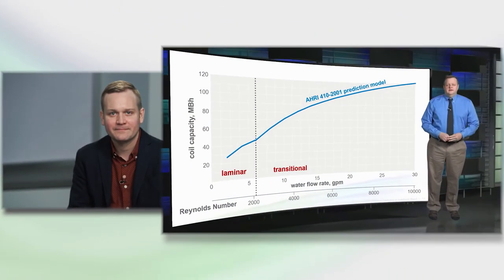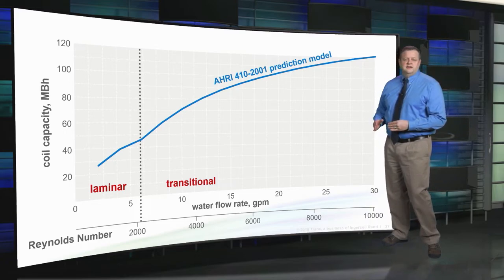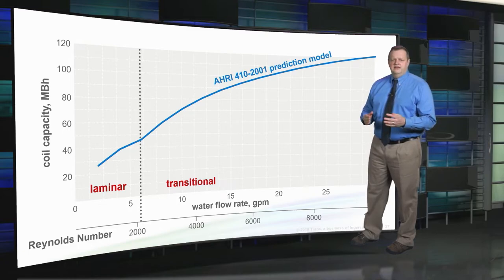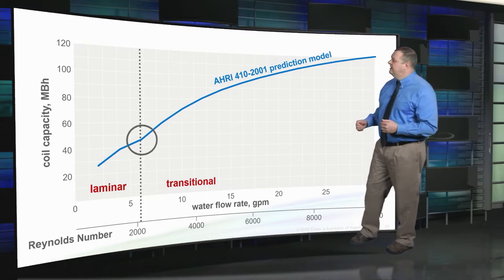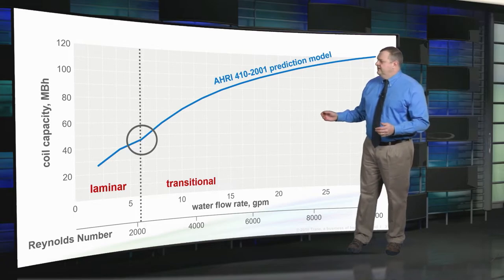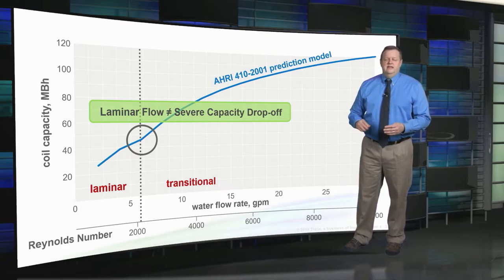Back in 2015, Trane produced an ENL on coil selection and optimization, interviewing a 20-year veteran of the AHRI 410 Engineering Committee to address this concern. He showed how the AHRI prediction methodology was refined in 2001, allowing coils to be accurately rated well into the laminar flow region without fear of large discrepancies between predicted and actual performance. A chart plotting coil capacity versus water flow rate and Reynolds number shows only a slight dip in capacity in the laminar region — nothing drastic. In summary, laminar flow does not cause a severe drop-off in capacity.